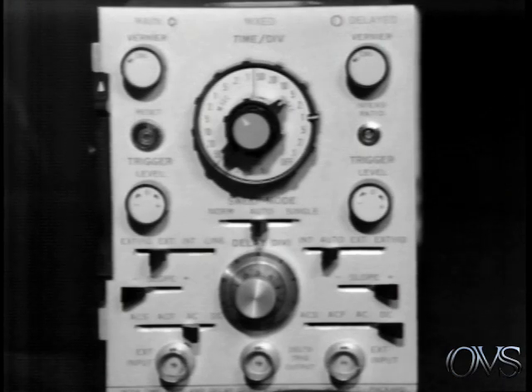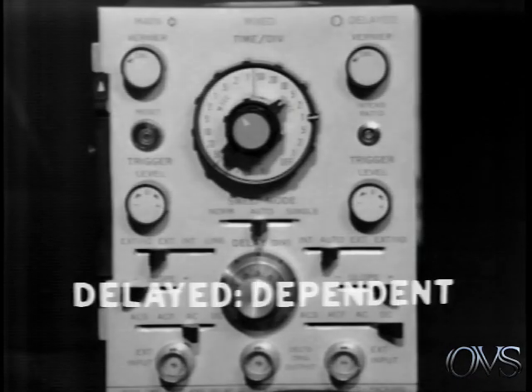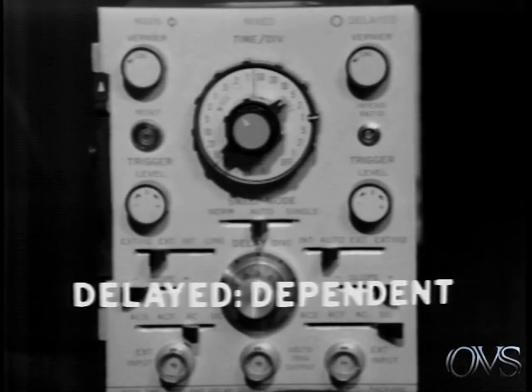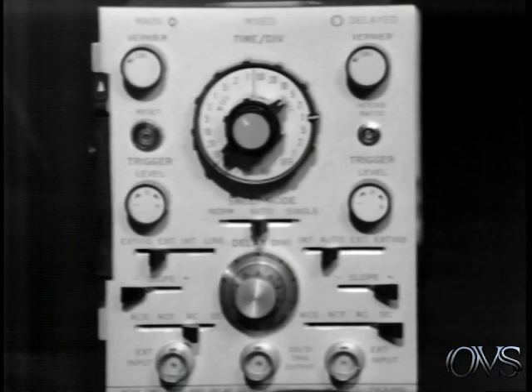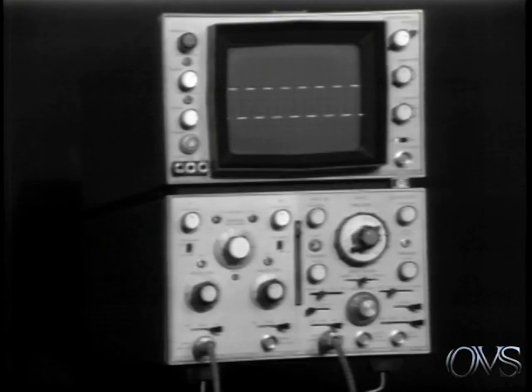It is important to remember that the delayed sweep is the dependent sweep. That is, it's dependent on the main sweep because it is armed by the main sweep only after an adjustable delay period. Now, before we go into the uses of the delayed time base generator in our digital applications, let's briefly review the operation of a delayed time-based sweep. And to do this, we'll use a second oscilloscope to monitor the waveforms inside the 1821A.